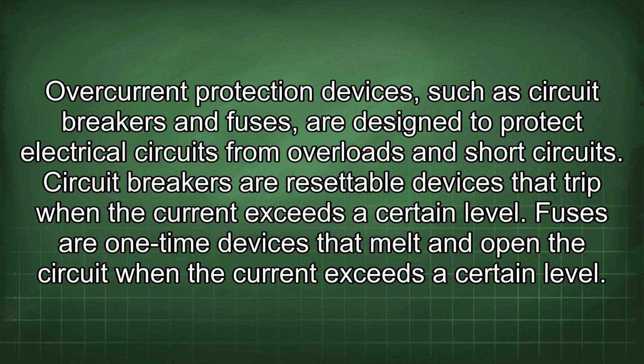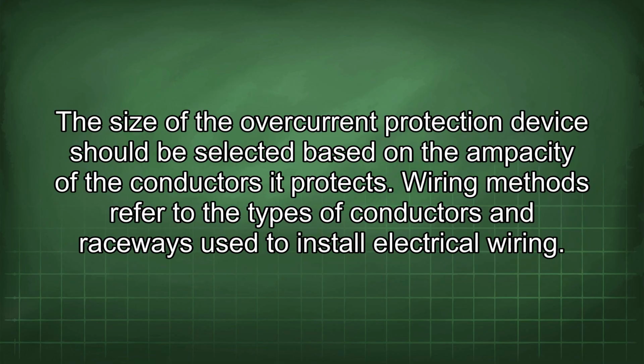Overcurrent protection devices, such as circuit breakers and fuses, are designed to protect electrical circuits from overloads and short circuits. Circuit breakers are resettable devices that trip when the current exceeds a certain level. Fuses are one-time devices that melt and open the circuit when the current exceeds a certain level. The size of the overcurrent protection device should be selected based on the ampacity of the conductors it protects.